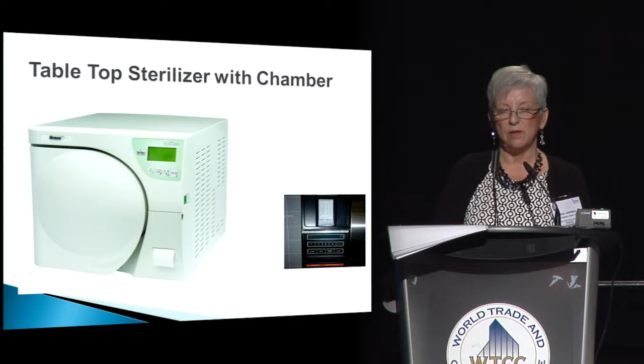sterilizers. This one here is more of a tabletop one, and you can see that the trays are loaded in this particular picture. Level or on top, but there's a good space in between each. They don't touch the sides of the chamber, so if the space is not there, or the tray touches the side of the chamber, it will cause a wet pack. In this particular one, this whole loading system can go on its side, so you can put your packages on the edge, so that if the device requires that, you can sterilize them like that.